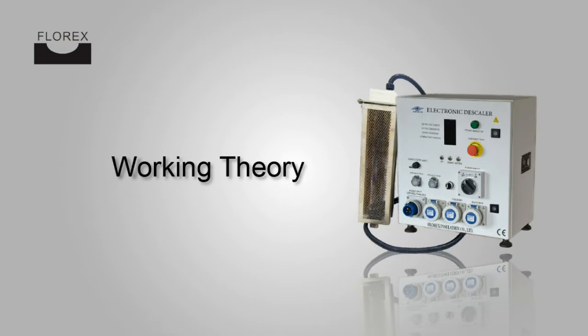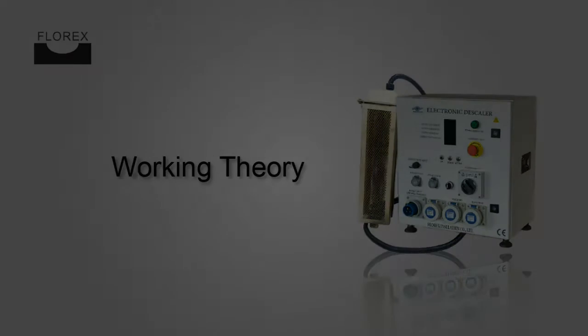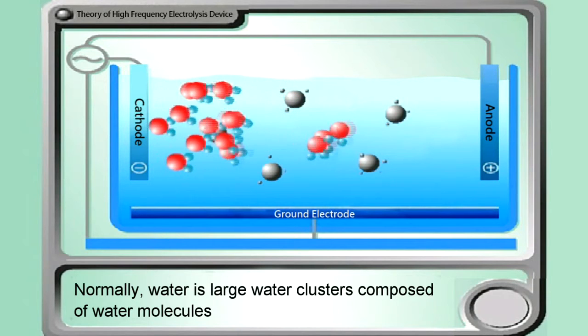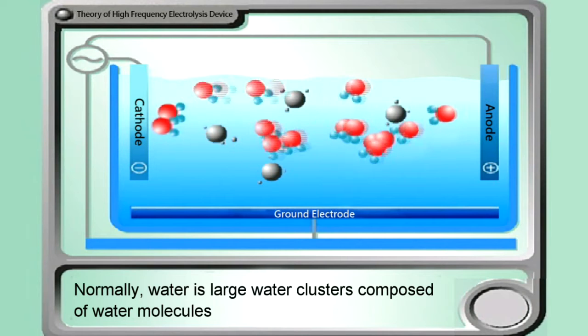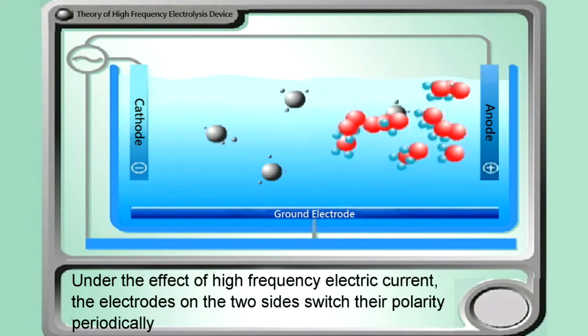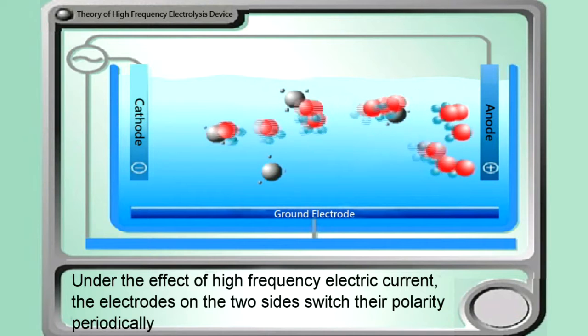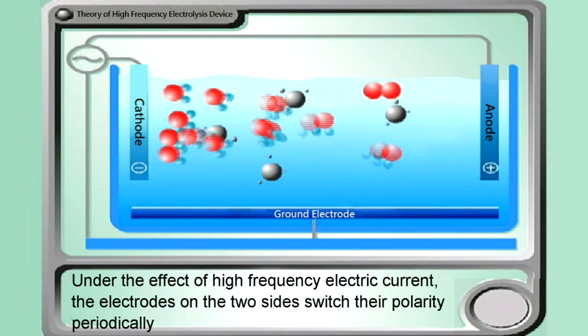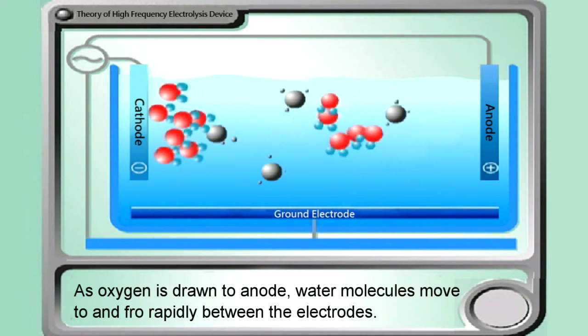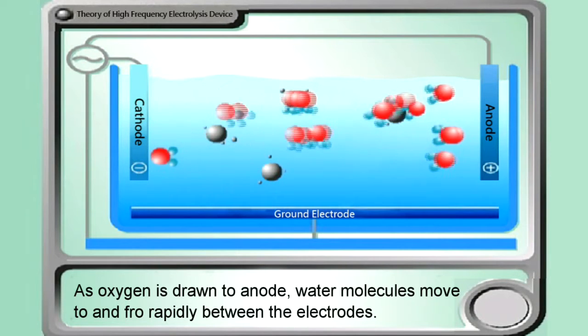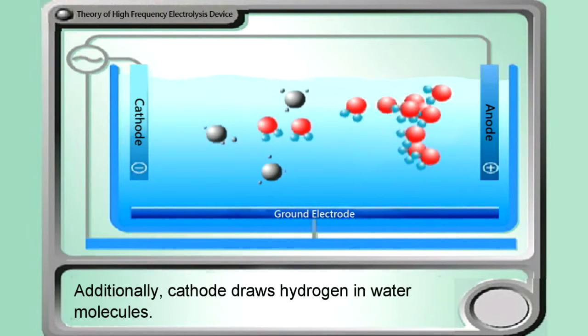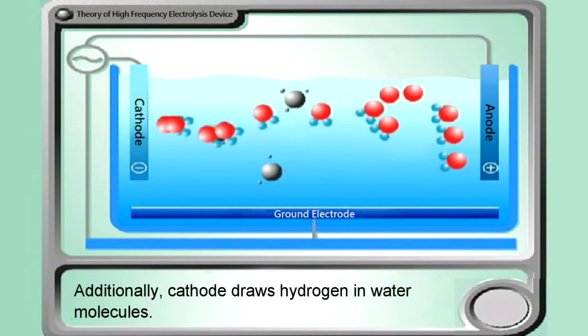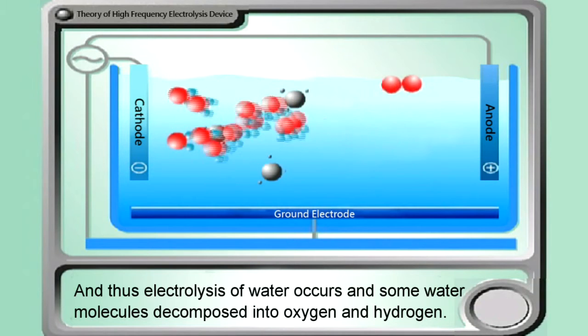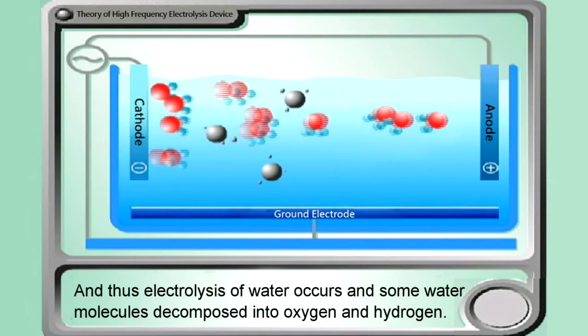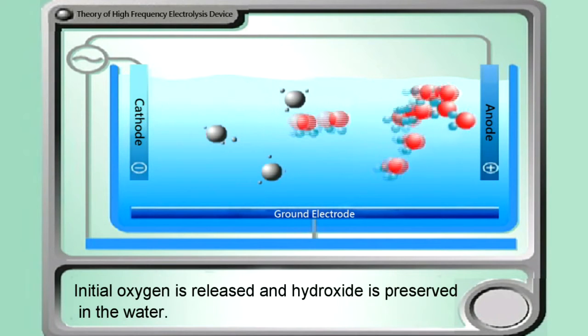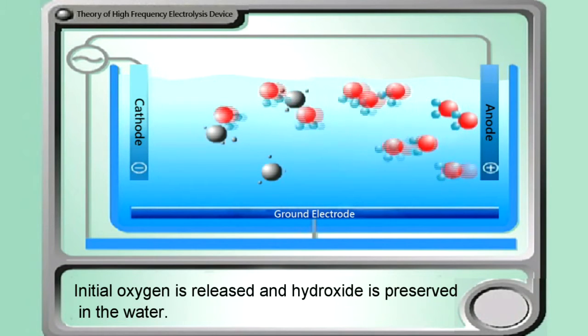Working theory. Normally, water is large water clusters composed of water molecules. Under the effect of high-frequency electric current, the electrodes on the two sides switch their polarity periodically. As oxygen is drawn to anode, water molecules move to and fro rapidly between the electrodes. Additionally, cathode draws hydrogen in water molecules, and thus electrolysis of water occurs, and some water molecules decomposed into oxygen and hydrogen. Initial oxygen is released, and hydroxide is preserved in the water.